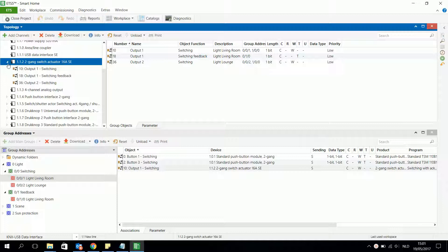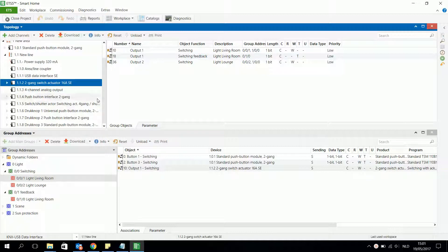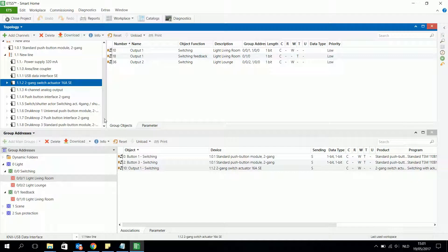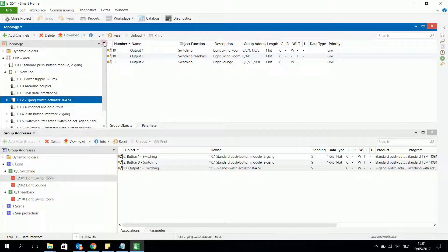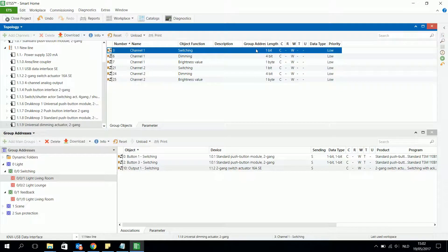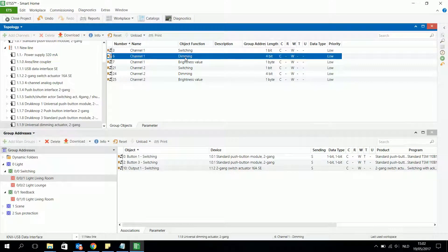It is only a switching actuator, so I have to look for a dimming actuator to really dim a light. In my list of actuators I find a dimming actuator. I can see that channel 1 has a switching object and channel 1 also has a dimming object, which is very important when I want to dim a light.